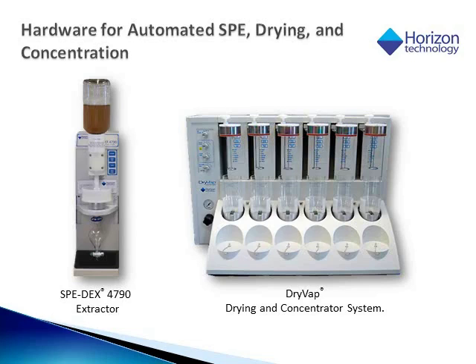Shown on the left is the SPE-DEX 4790 disc cartridge extractor, and on the right is the DryVap system. The DryVap system combines membrane sample extract drying and extract concentration down to a 1 milliliter volume automatically. The SPE-DEX 4790 processes one sample at a time and can be ganged in groups of up to 8. The DryVap system can handle from 1 to 6 samples independently or in batch mode.